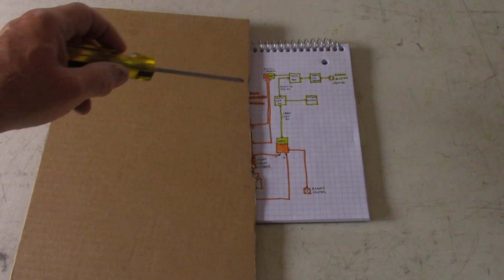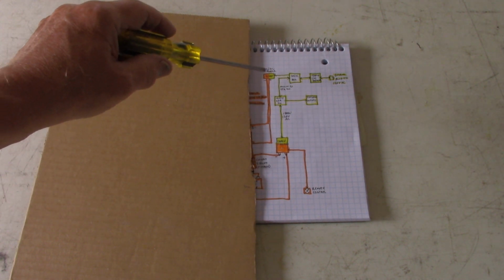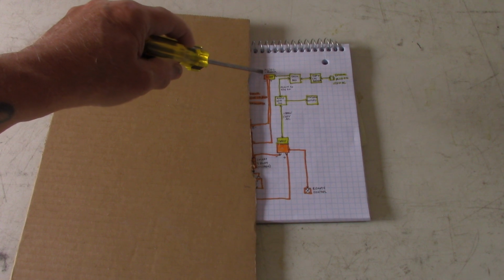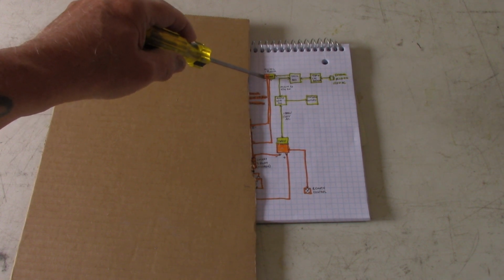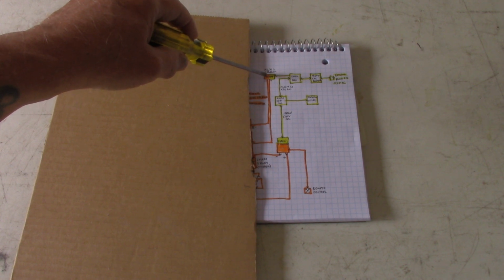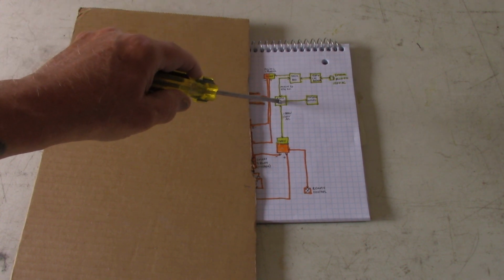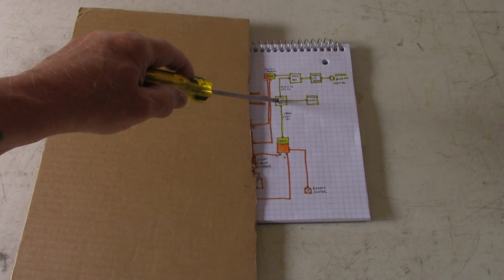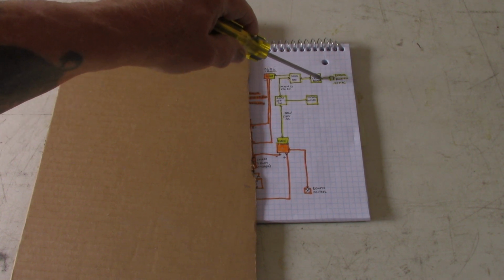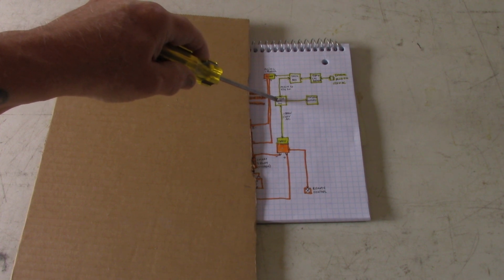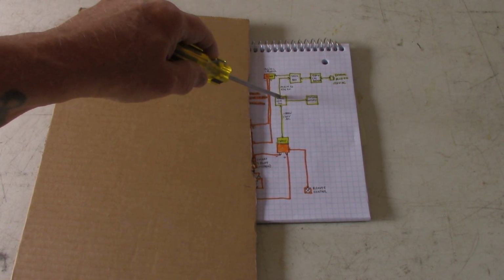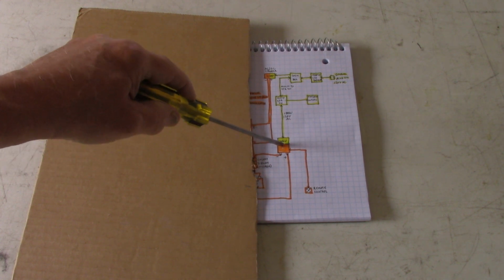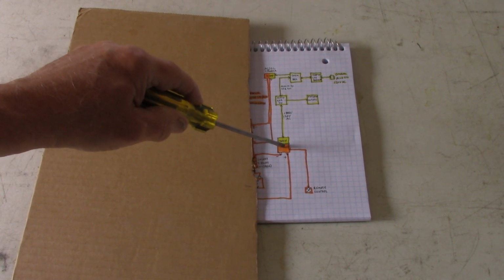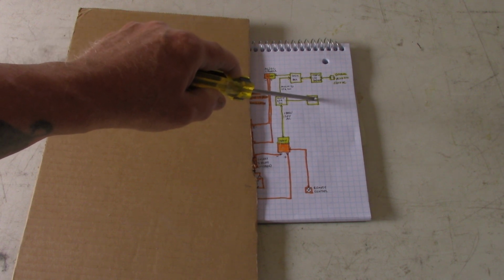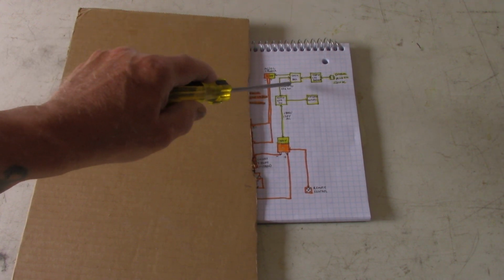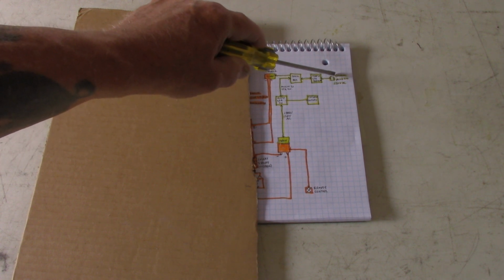What you see over here is the AC side. We have an AC DC 30 amp charger, so that's why it's going from AC to DC. And we also have an automatic transfer switch. It will transfer the 115 volt coming in and go to the interior outlets, or it'll switch back and forth to the 1000 watt inverter, which will provide 110 volt AC to the internal outlets.